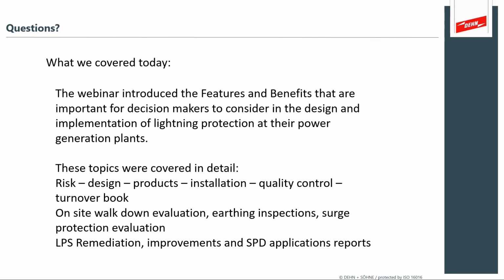Yeah, that's a really good point. And of course, that's really the intent of the air terminal placement. A big, tall steel structure may not actually explode if it's struck by lightning, but you don't want the lightning strike to attach randomly, because then it's going to get into the lighting and the instrumentation systems that are attached to these towers. So the whole point is to divert it safely into the steel of the structure, allow that steel to be the natural down conductor, and then divert it safely into earth. So remember, it's always about giving it a safe attachment point.